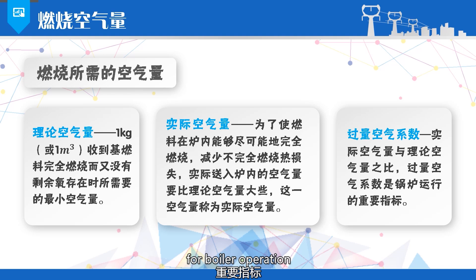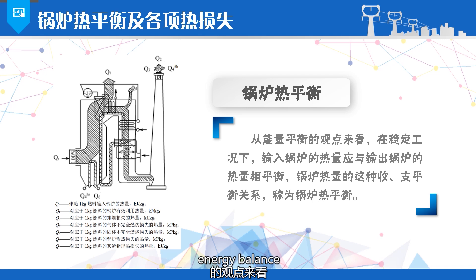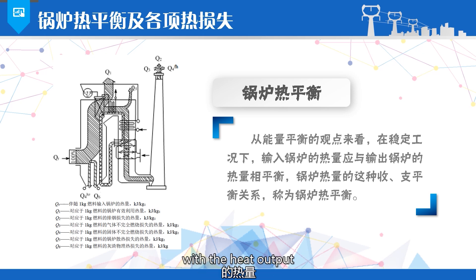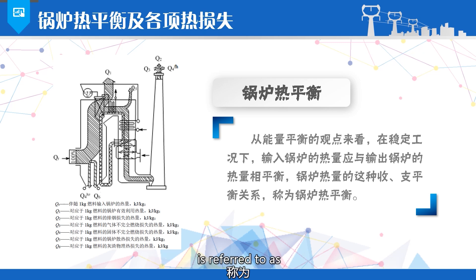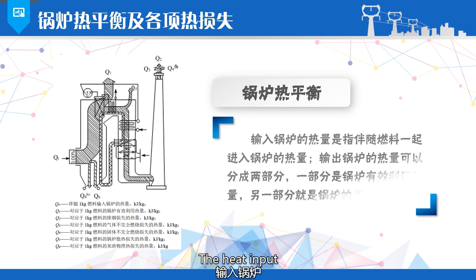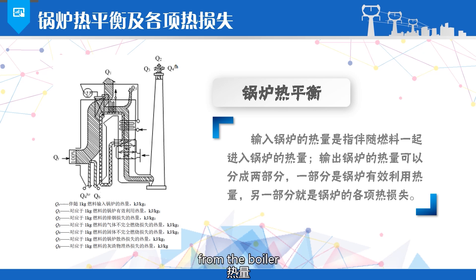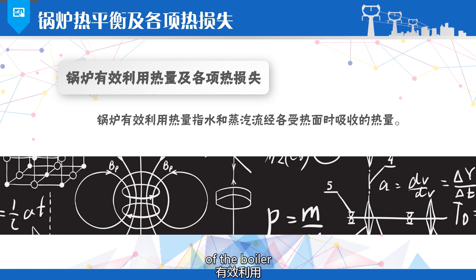The excess air coefficient is an important indicator for boiler operation. From the perspective of energy balance, under steady operating conditions, the heat input into the boiler should be balanced with the heat output from the boiler. This relationship of income and expenditure of heat in the boiler is referred to as the boiler heat balance. The heat input into the boiler refers to the heat that enters the boiler along with the fuel. The heat output from the boiler can be divided into two parts: one part is the effective heat utilization of the boiler, and the other part is the various heat losses of the boiler. The effective heat utilization refers to the heat absorbed by the water and steam as they pass through the various heat transfer surfaces.